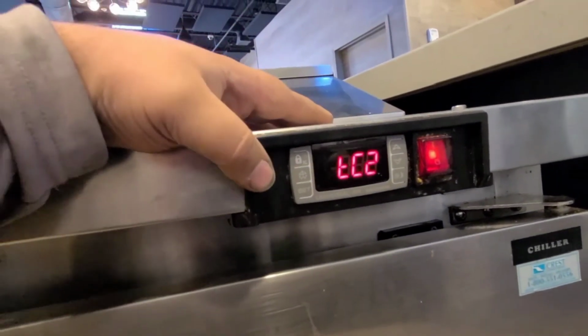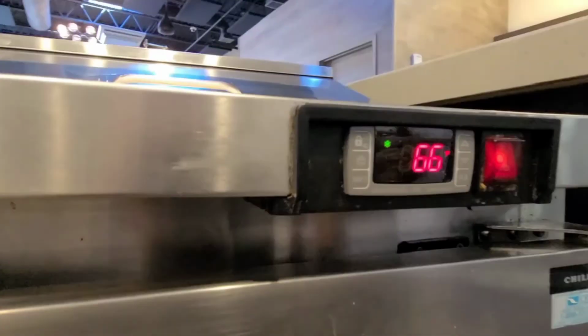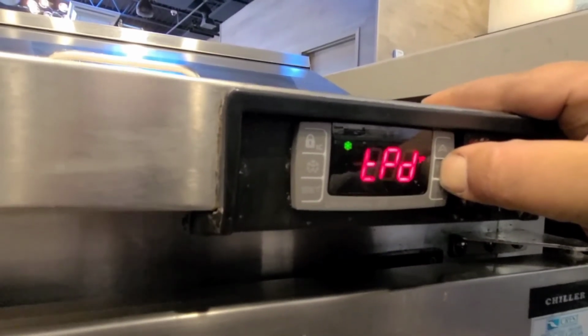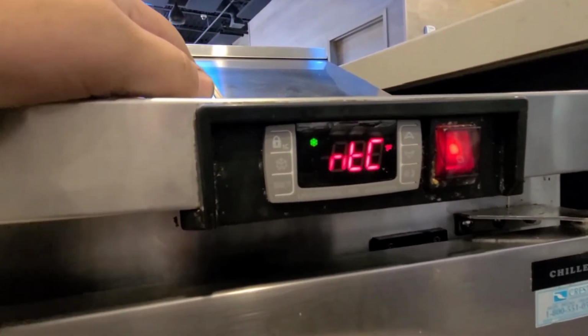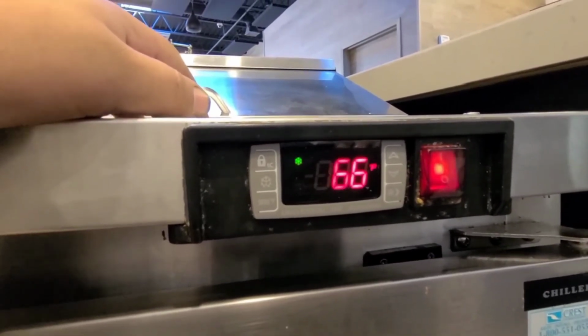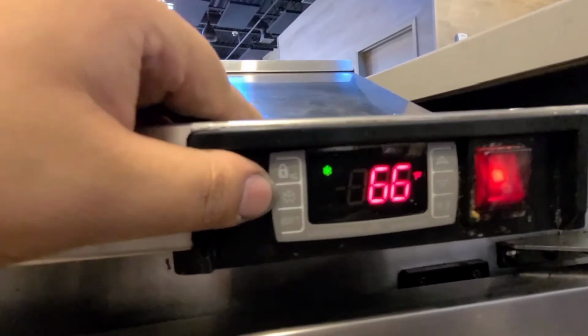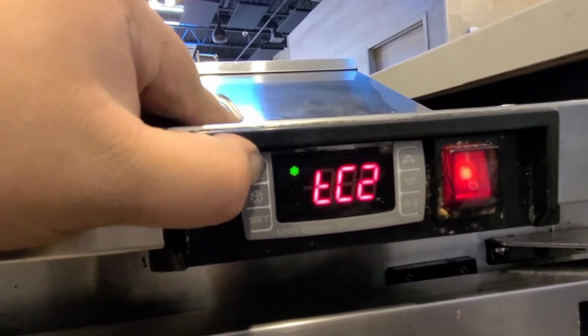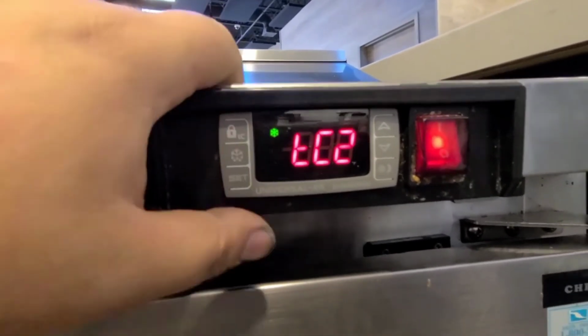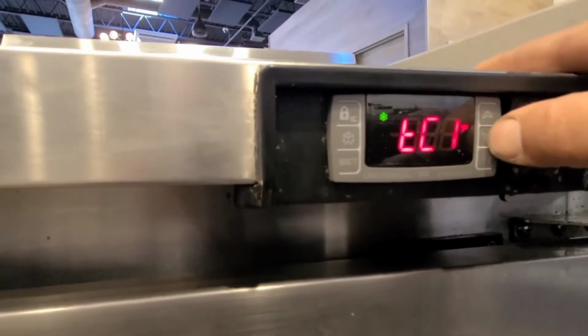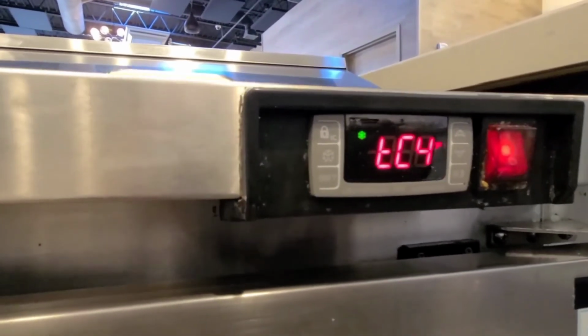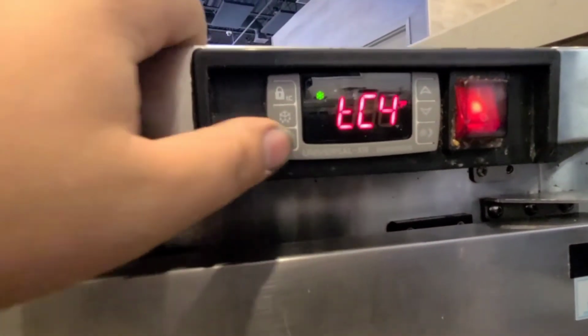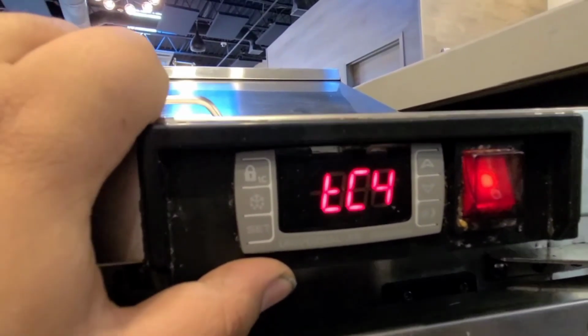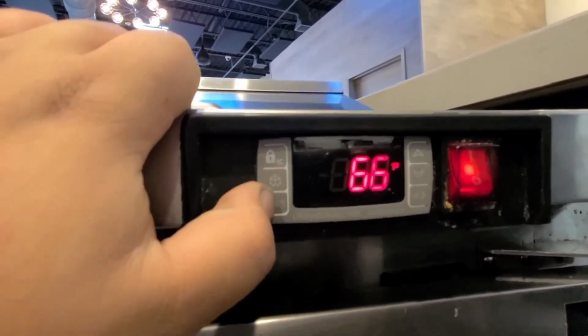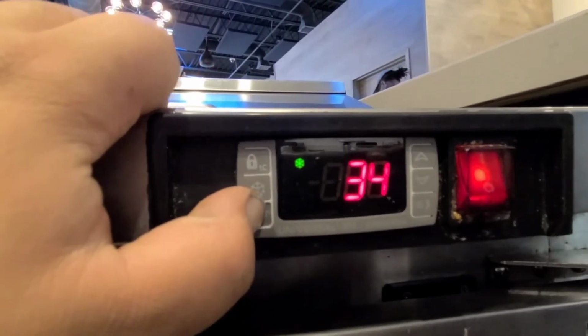So let me go through these steps real quick. Alright, power's on. So it's trying to adjust and recognize the sensors that are in it. Hold that button down. NTC. Alright. I gotta hold down auxiliary TC. Hold that button down. So now I'm gonna set that one to 4, like I said, for defrost off cycle. Save it, then you hold set. Make sure the set temperature is where I want it to be. 34 degrees, I'm happy with that.